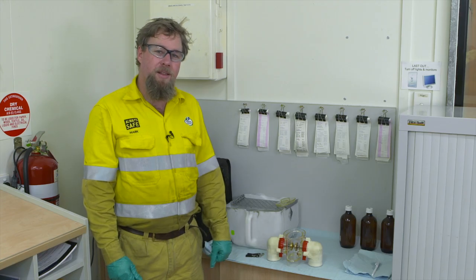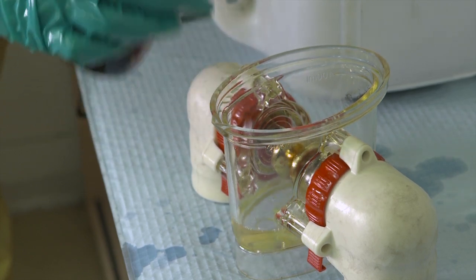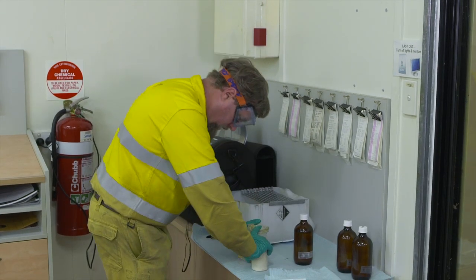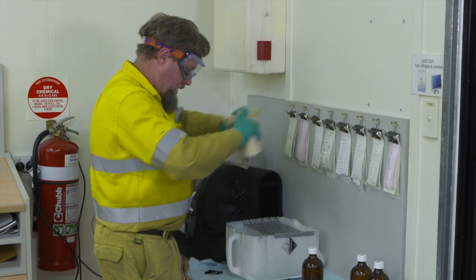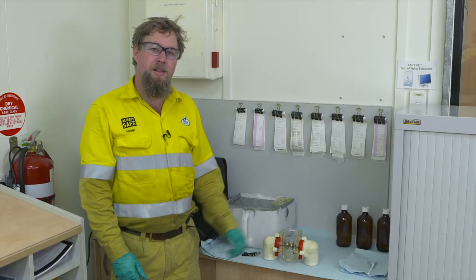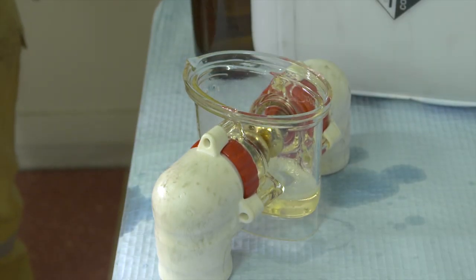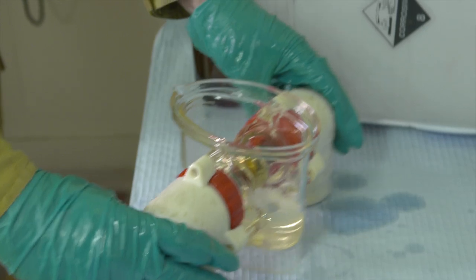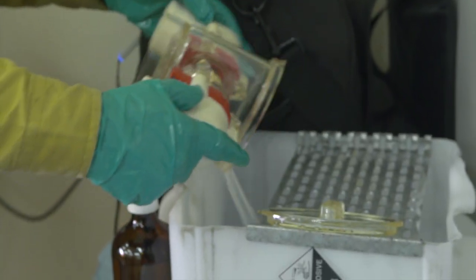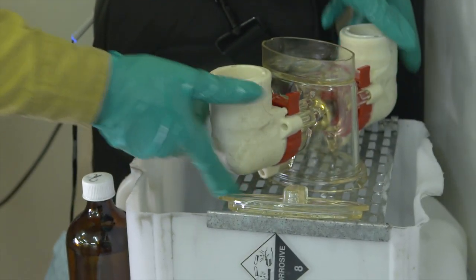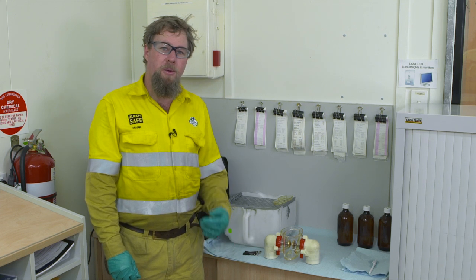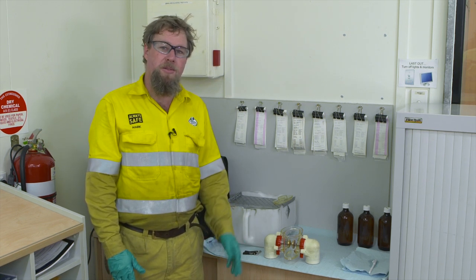When cleaning, the electrodes should just be washed out with clean oil. Do not use any cloths or solvents or anything like that; just straight clean oil will be sufficient. If cloths are used, they can leave little fibres around the electrodes, which will give you a false reading or a bad result when you are comparing with your other results.